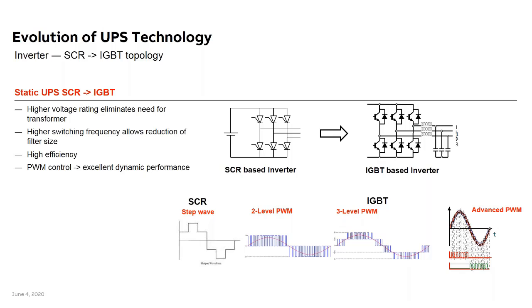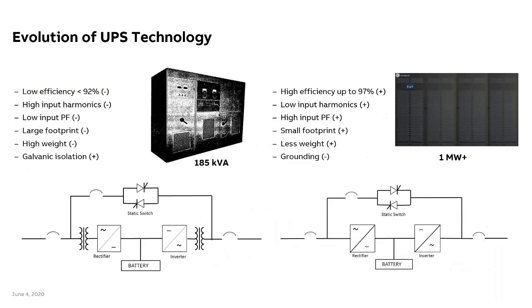We've seen two-level inverters, primarily with the bipolar transistors, and then lately most UPSs are based on three-level PWM, and it's all about getting a waveform that's as close to an ideal sine wave as possible. It's still tiny little square waves, but very close to an ideal sine wave. So UPSs still need filters to filter the harmonics out and make it a sine wave, but very, very small compared to 50 years ago, or even 20 years ago. So a little technology.